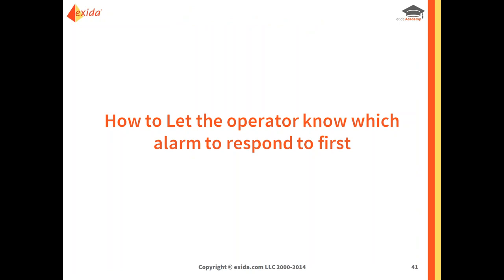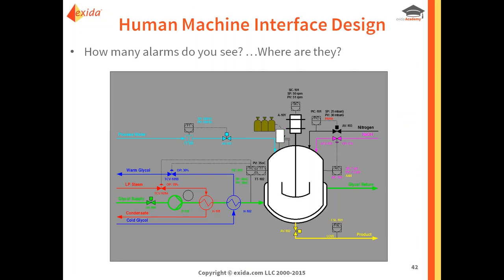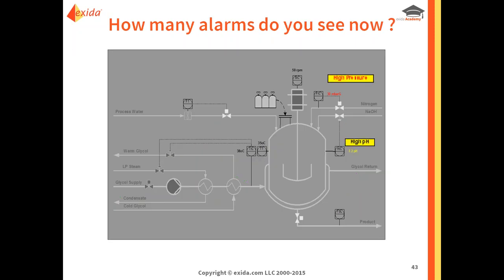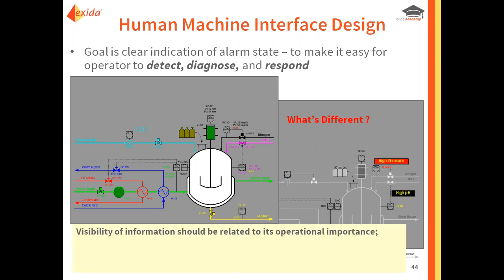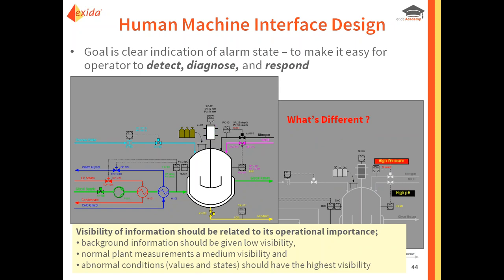How do you let the operator know which alarm to respond to first? This primarily comes down to the HMI — the human-machine interface — which should draw their attention and communicate which situation is most critical. A well-designed HMI makes alarms stand out clearly; they should jump off the page. By contrast, a poorly designed screen makes alarms difficult to distinguish. The coloring, priority, and visibility within the HMI should correlate to how important or critical the alarm is.